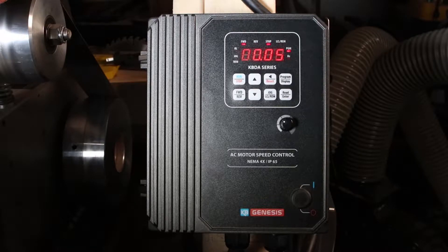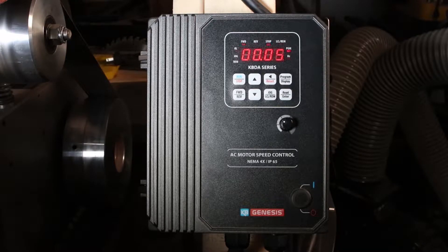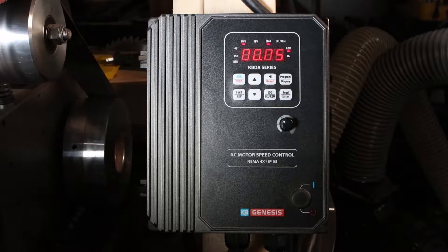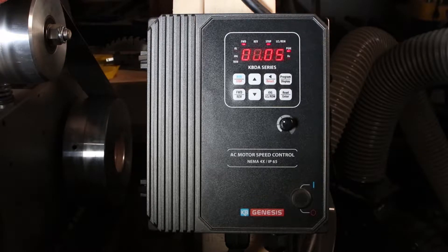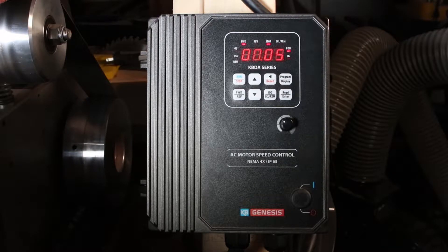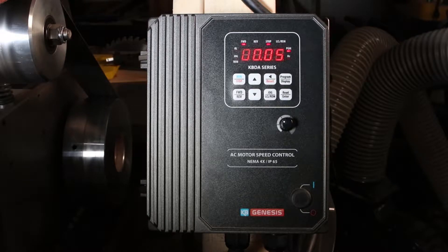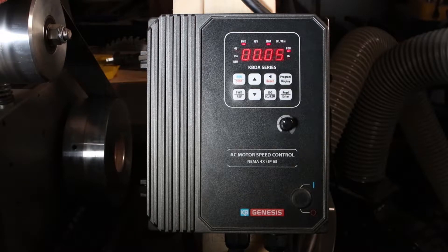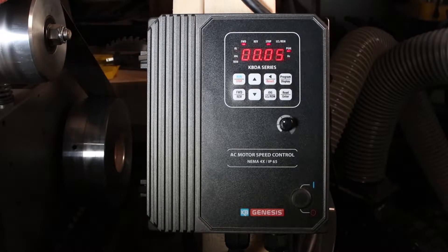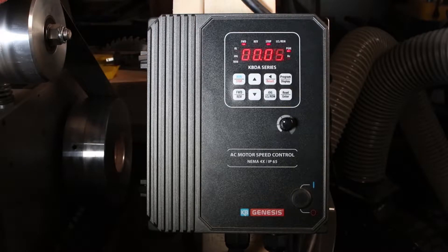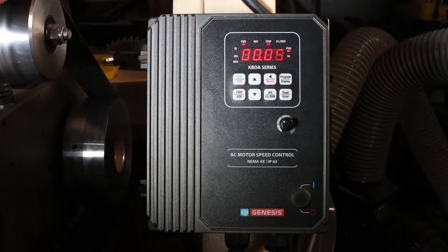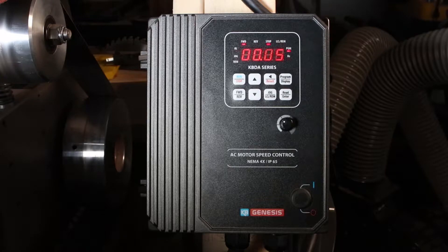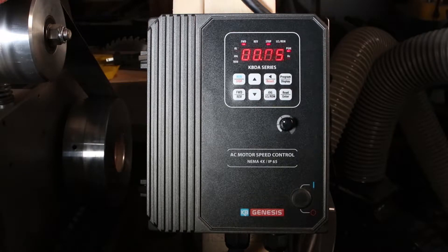So for example, if my memory serves correct, a two horsepower motor, let's say 1800 RPM motor running at twice the speed, 3600 RPM at 120 Hertz, loses 75% of its torque. So at 3600 RPM, that motor is really a half a horsepower motor.